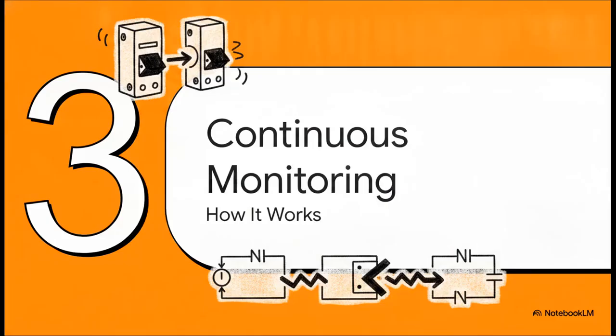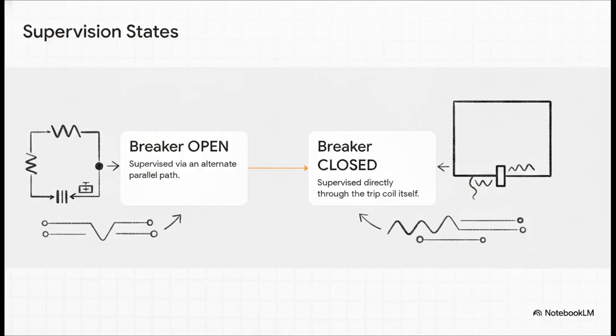Section 3. How continuous monitoring works. Now here is where the engineering gets super clever. A circuit breaker isn't just a static device, right? It opens, it closes, it physically shifts the circuit's topology. So how on earth does the relay adapt to keep that continuous test signal flowing? Well, when the breaker is closed, the supervision current flows right through the trip coil itself, proving the primary path is intact. But when the breaker is open, that main path might be physically interrupted by auxiliary contacts. So the TCSSCBR function seamlessly shifts to supervise the circuit using an alternate parallel path. It makes sure the test signal is literally never broken.